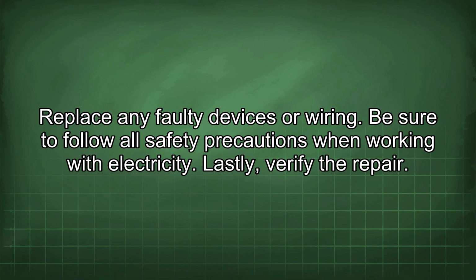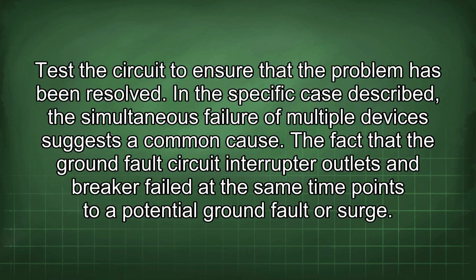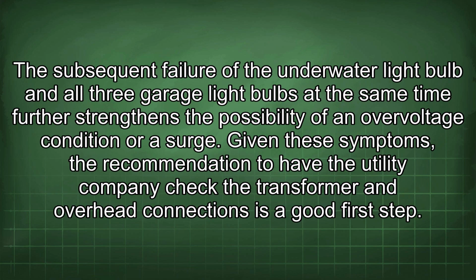Lastly, verify the repair. Test the circuit to ensure that the problem has been resolved. In the specific case described, the simultaneous failure of multiple devices suggests a common cause. The fact that the ground fault circuit interrupter outlets and breaker failed at the same time points to a potential ground fault or surge. The subsequent failure of the underwater light bulb and all three garage light bulbs at the same time further strengthens the possibility of an overvoltage condition or surge.